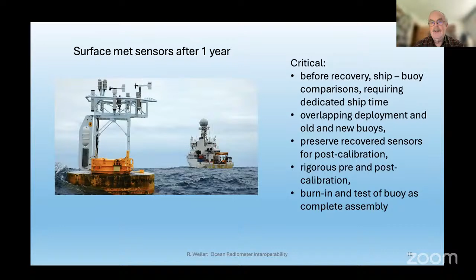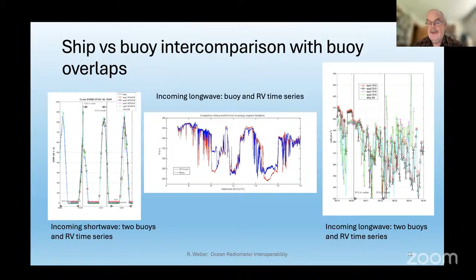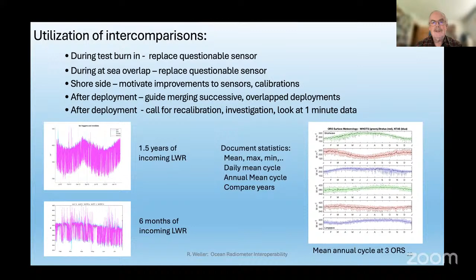We overlap buoy deployments. We try to compare the shortwave and the longwave between the old deployment and the new deployment. But if you look at intercomparison plots of incoming longwave on the right, where both the research vessel and the two buoys are plotted, I don't know how to make a lot of sense out of that. There's a lot of scatter in those measurements. We keep doing these intercomparisons. When we burn buoys in before deployment, we compare the two or three pyrgeometers on it. If it's questionable, we replace it. When the buoy goes over the side and we compare to the ship, if the pyrgeometer or any instrument is questionable, the guys get in a small boat and they replace the sensor. When we come back, we compare the several redundant measurements on the buoy and we compare statistics.